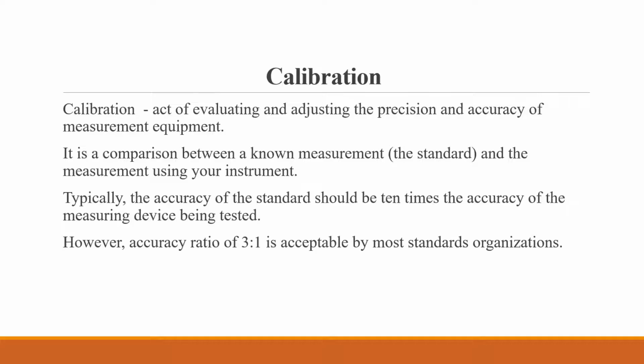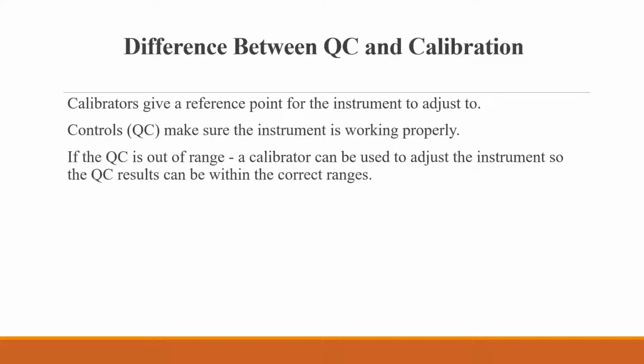The difference between quality control and calibration: calibrators give a reference point to the instrument to adjust to, and controls or quality control make sure the instrument is working properly.